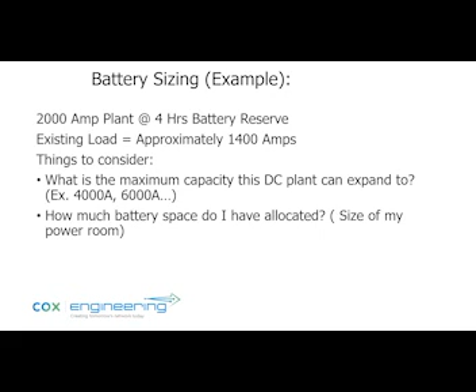Usually it's from 36 to 60 volts, but some equipment on the floor will cut out at about 42 volts, so let's say it's 43.12. You've got to find this out for each site. Then we have a 2-volt drop, because from the battery terminals to the end-of-line equipment in the racks there's a lot of copper involved, and wherever you have copper you have I-squared R, current squared times resistance losses, which again is Ohm's law. That's why high voltage lines use such high voltage, so they can travel long distances. For DC cables, as in the AC world, we engineer for a 2-volt drop from the battery terminals to the end of the line, meaning we need 45.12 volts at the battery terminals.